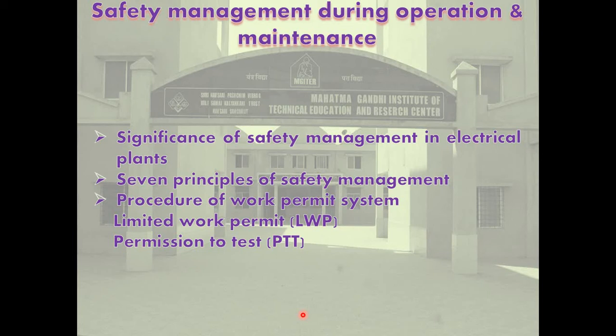Many ignorant technicians defeat such safeguards, thereby the risk of accidents increases. During commissioning, some relays and protection systems are bypassed in a hurry to commission, resulting in tremendous risk. A good site safety management prohibits such lapses by strict field quality checks and tests at every stage of the project. Formerly, accidents were attributed to individual mistakes. This theory is no more acceptable.